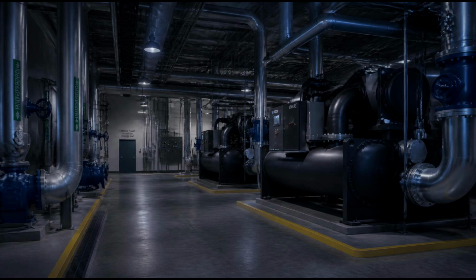Some carries the heat that has been removed from the building to the cooling towers above. And all of it is kept moving by pumps. Pumps move water through many commercial HVAC systems. Pumps are among the most reliable and unassuming pieces of equipment in the entire building. They do not transform anything. They do not change the temperature of the water or alter its chemical composition.